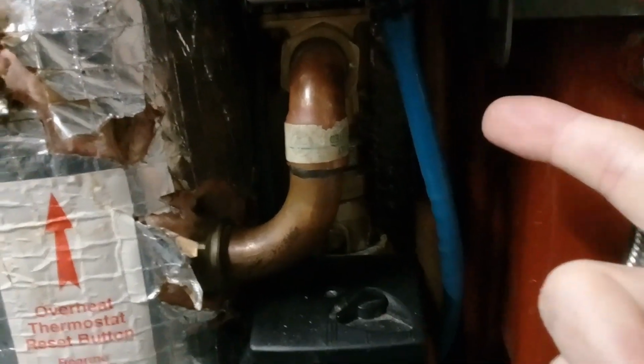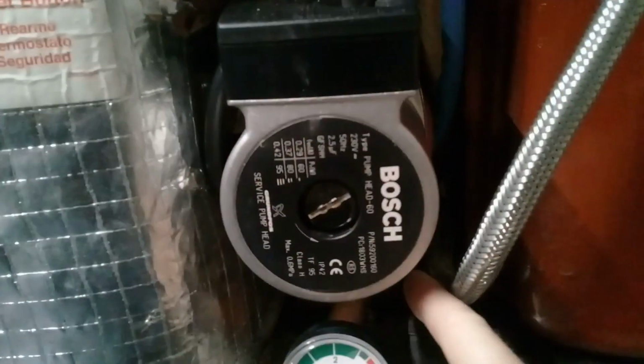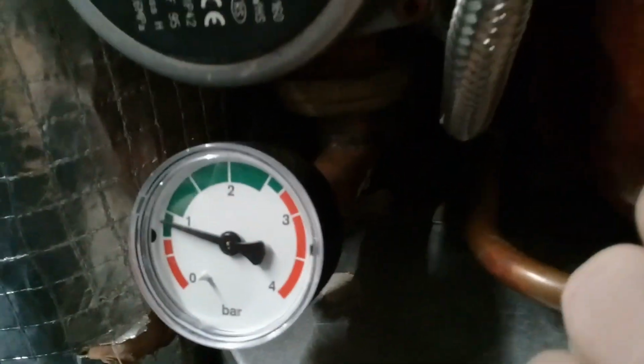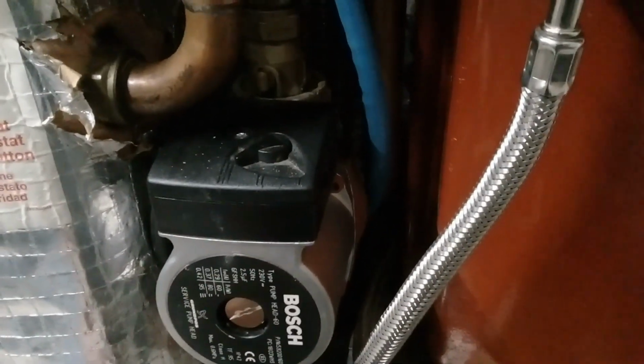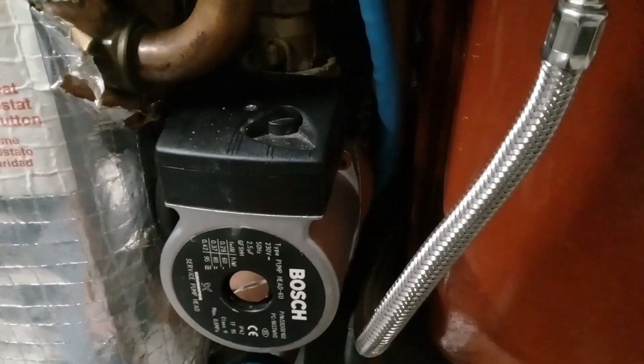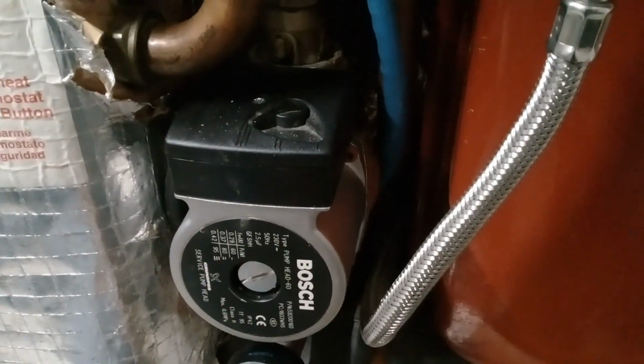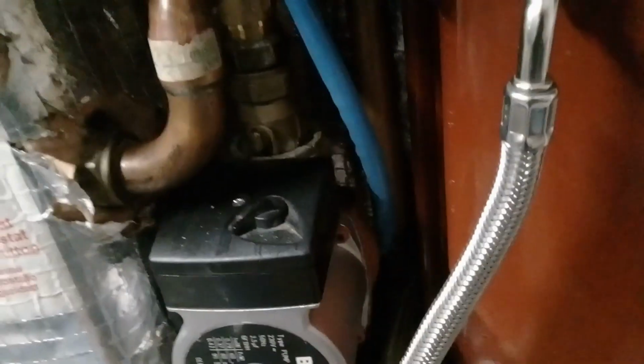the central heating's triggered. So here we've got the main body of the system with the water that comes through the main heat exchanger of the boiler. So my symptoms were central heating on. When you touch these pipes either side of the pump, they're either cold or lukewarm, so there's no circulation. So you start thinking, blockage. Not the diverter valve. No water is coming through the pump, past the pump. So straight away you think, this is not right.